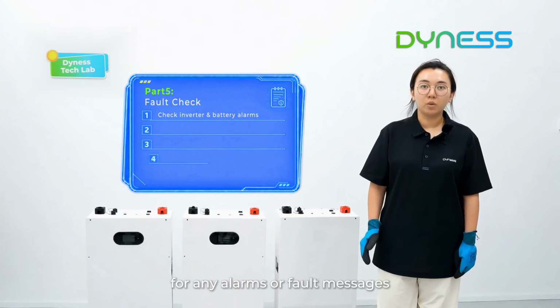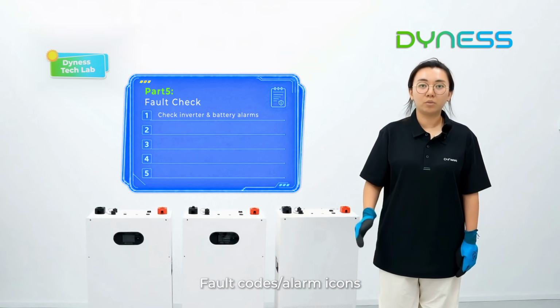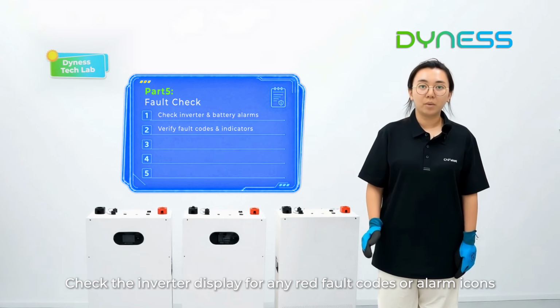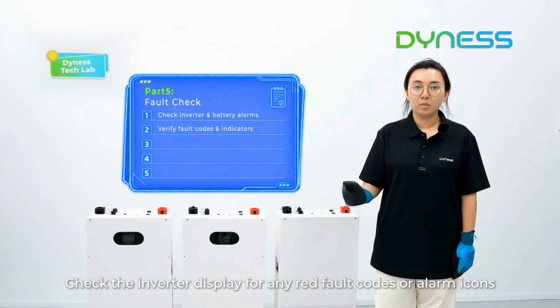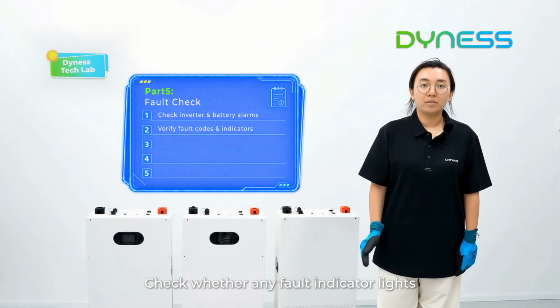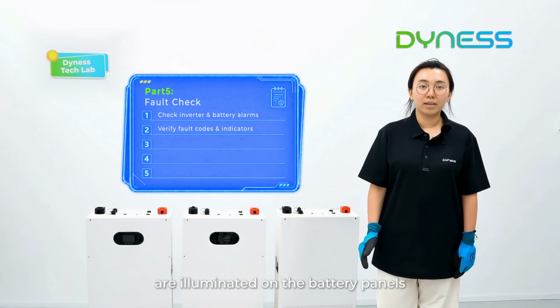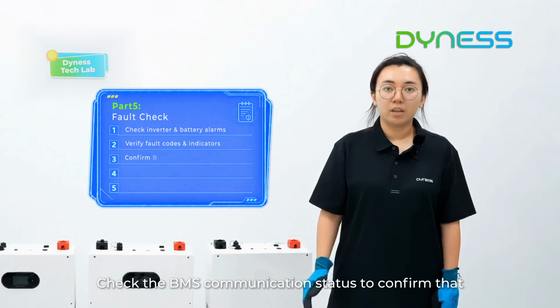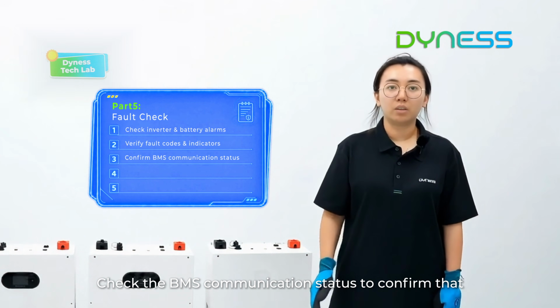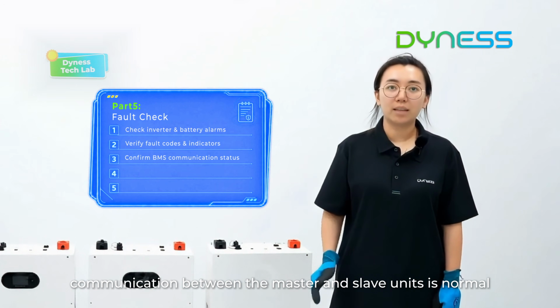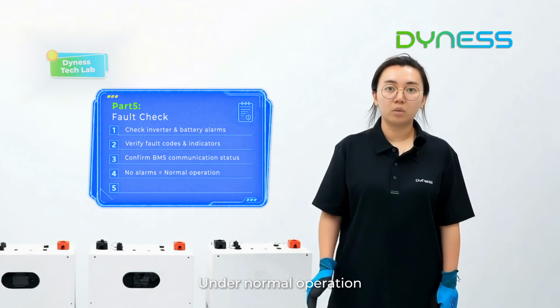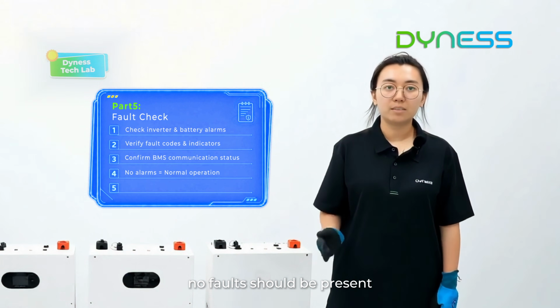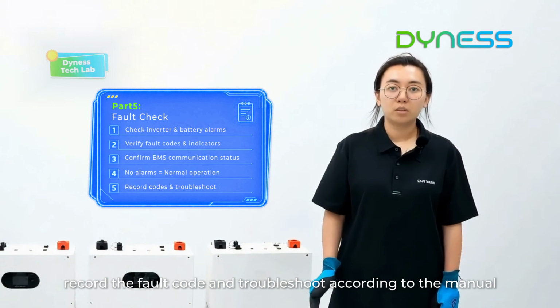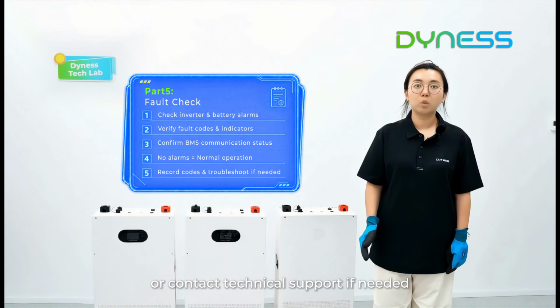Check both the inverter display and battery panels for any alarms or fault messages. Focus on fault codes, alarm icons. Check the inverter display for any red fault codes or alarm icons. Warning indicators. Check whether any fault indicator lights are illuminated on the battery panels. Communication status. Check the BMS communication status to confirm that communication between the master and slave units is normal. Under normal operation, no faults should be present. If any issue occurs, record the fault code and troubleshoot according to the manual or contact technical support if needed.